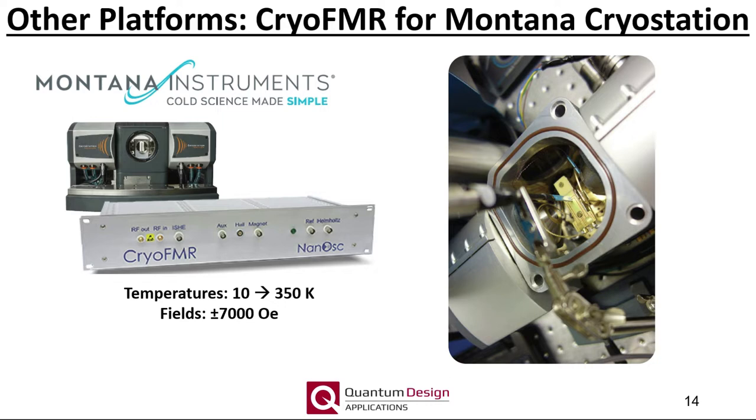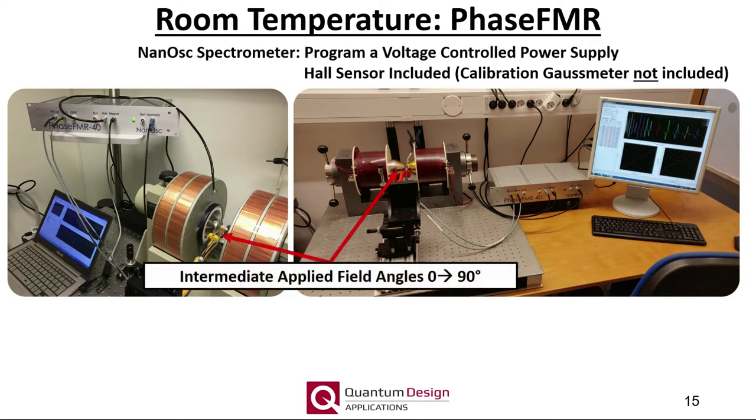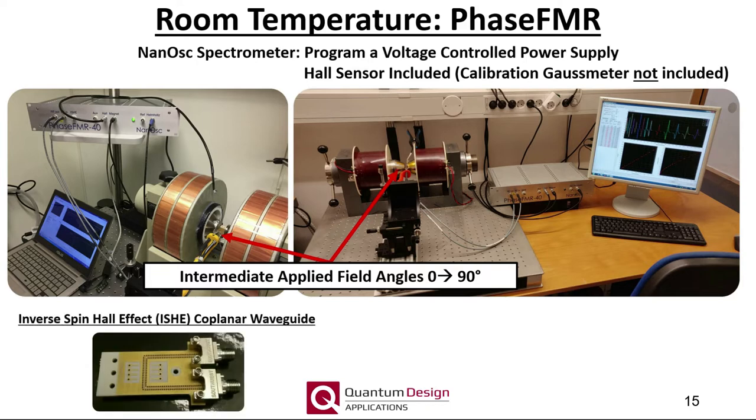The cryo-FMR instrument can also be integrated into other magneto-cryostats on the market — please contact your local Quantum Design office for more information. The Phase FMR spectrometer is intended for room temperature applications which use an electromagnet. While the NanOsc instrument cannot energize an electromagnet, it can control a suitable voltage-programmable magnet power supply. One benefit of a room temperature setup is the ability to easily set applied field angles between 0 and 90 degrees. A specialized inverse spin-Hall effect coplanar waveguide also exists for the Phase FMR product line.